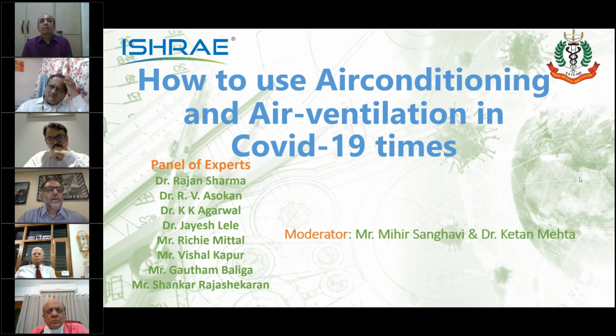Okay, thank you. There's a question with regards to air purifiers. You are saying bring in outside air, but what about the Delhi smog when the outside AQI is 400, 500, 600? I think I just answered that question. If you're bringing in a lot of outdoor air, an air purifier will very quickly start failing. It will not be able to effectively filter out that level. When an air purifier is designed or selected, it is meant for recirculating the air within the premises. Bringing in a large amount of outdoor air for an air purifier is self-defeating the whole purpose of installing the air purifier.